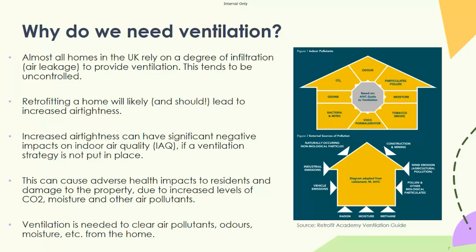We've got these, frankly, pretty poor intermittent extract fans in our wet rooms that wouldn't be unusual to be whirring backwards with a bit of a wind against them, or clogged up with dust and not actually delivering much in the way of extraction, or they're very noisy and ineffective. And so aside from that kind of minor intermittent extract provided by the fans, your air changes are almost entirely delivered by the inherent leakiness of the building.